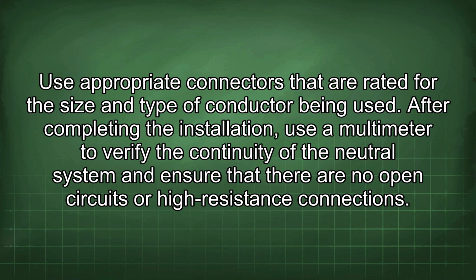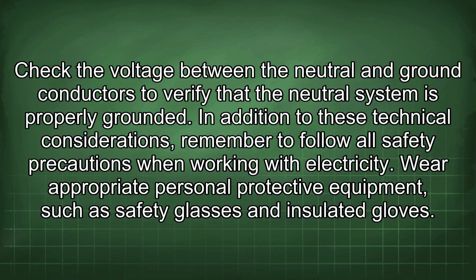After completing the installation, use a multimeter to verify the continuity of the neutral system and ensure that there are no open circuits or high-resistance connections. Check the voltage between the neutral and ground conductors to verify that the neutral system is properly grounded. In addition to these technical considerations, remember to follow all safety precautions when working with electricity.